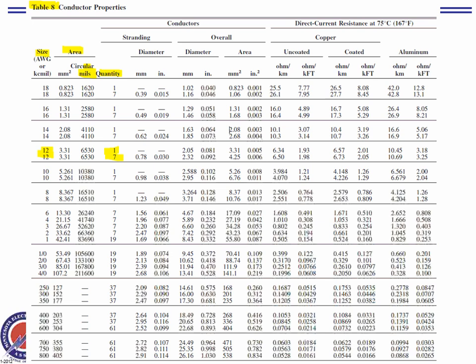All right, let's go to DC. Here's the resistor for Mr. Copper or Mrs. Aluminum. Your default is always coated or uncoated. It's coated and uncoated. Unless they tell you it's coated, your default is what? Uncoated copper. What's the impedance for a solid copper number 12? It's 1.93. If it's stranded, it's 1.98. Okay? Make sense? Now if it's aluminum, you have 3.18 and 3.25 for solid and stranded. Am I making sense, everybody? Can you guys see how to find R? This is table 8, chapter 9. Table 8, chapter 9.